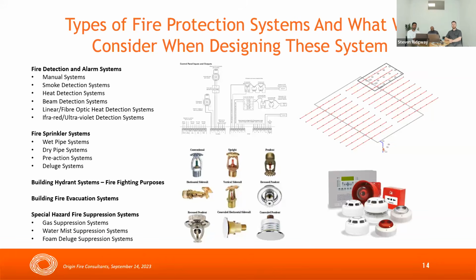There are other types of fire suppression systems which can be utilized to cater for specific risks in a building. These are, as an example, gas suppression systems and water mist systems. Typically in data centers, a sprinkler installation could severely damage servers if it were to operate. A water mist system is better suited, as the water mist particles are able to suppress a fire while not damaging sensitive electronic equipment. A fire protection engineer needs to have a strong understanding of the different types of applications of fire detection and suppression systems, as there are quite a few manufacturers of these systems.